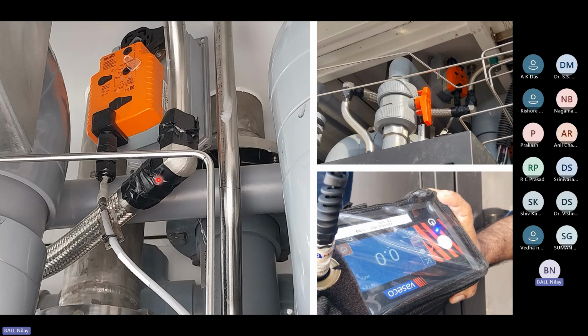You have to be an expert, because the moment you insert it, the value will show high, and then the helium leaks through the leakages and you won't get that value. So if there's a spike here, you tape it up again, give it time for the leakage to accumulate, and redo the testing.